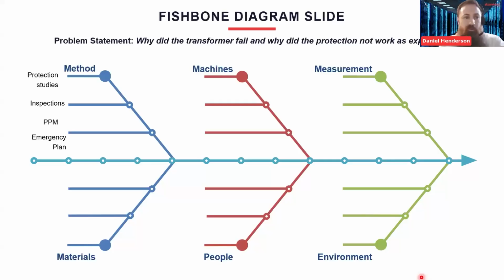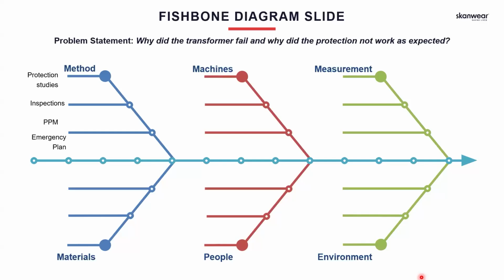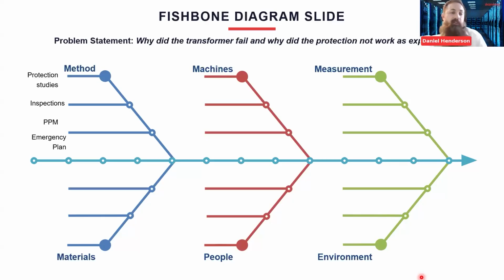Was there anything in the chat on method? There's just one note here. It's also worth checking that the protection settings at the relay match the settings in the protection study or master schedule. This issue was mentioned in the last webinar around validity of arc flash calculations. 100%, definitely. On this one, we'll cover it when we go a bit deeper, but essentially they were matched because it was done after the design was done. It had been around a long time, so we probably had multiple studies by then. But the settings are definitely something to look at as part of this.